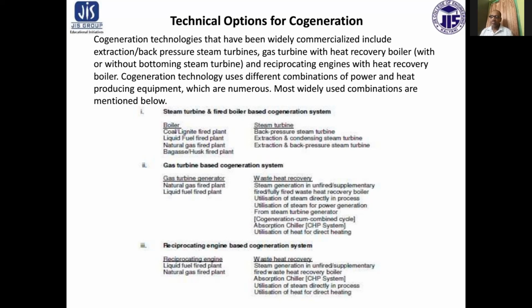Third is the reciprocating engine based cogeneration system. The reciprocating engine may be a liquid fuel fired plant or a natural gas fired plant. The waste heat recovery may be done by steam generation in an unfired or supplementary fired waste heat recovery boiler. Waste heat may also be recovered by absorption chillers, and may be used as steam directly in the process or for direct heating purposes.